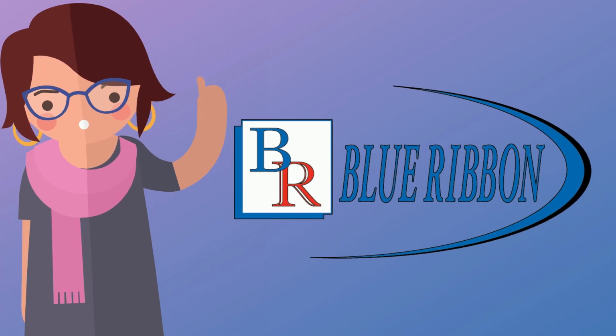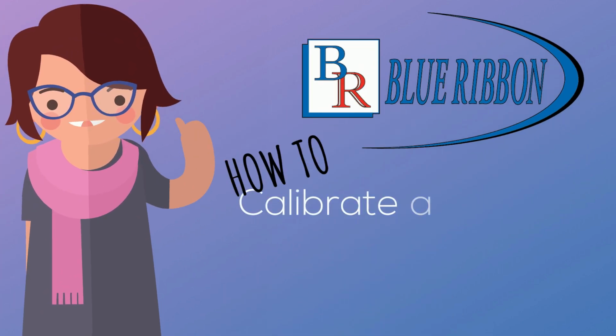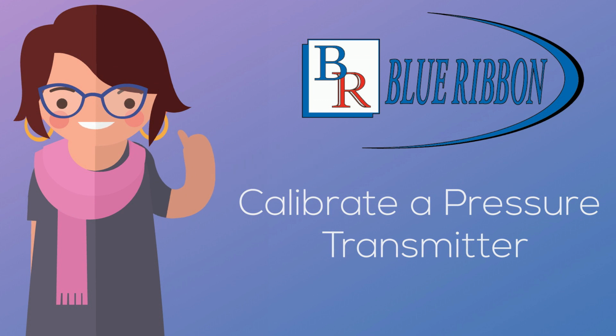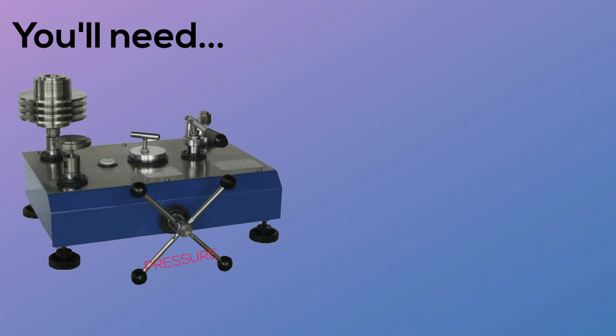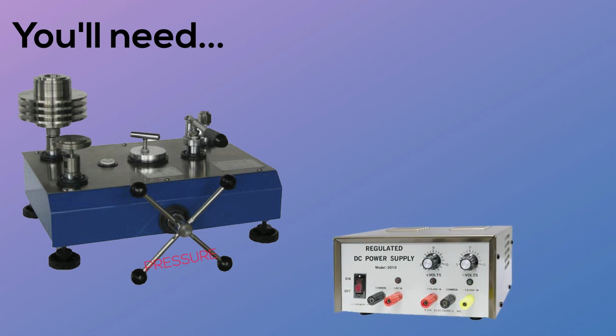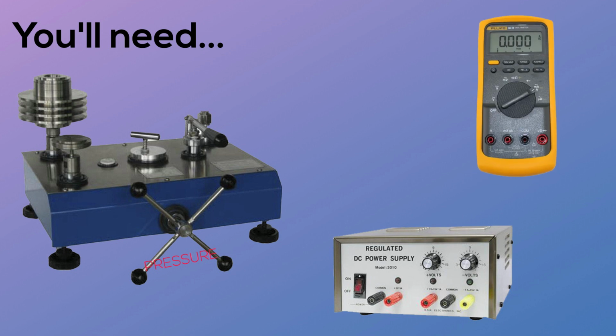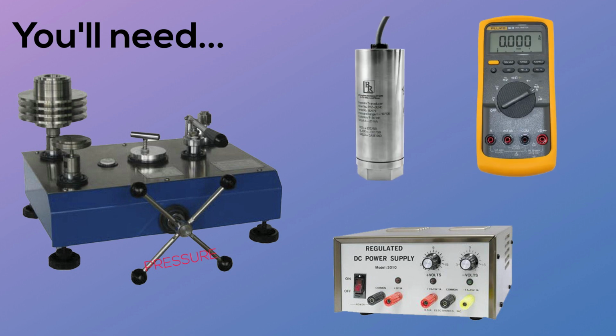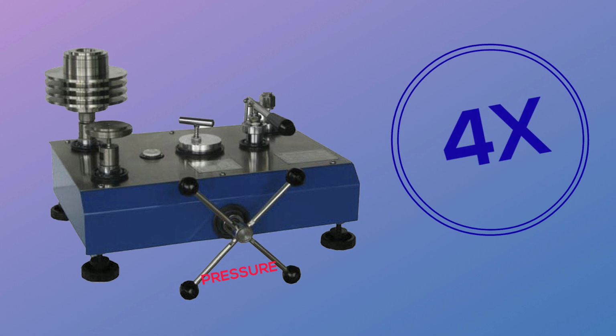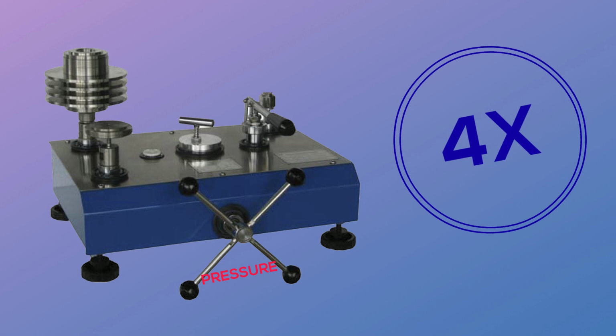In this video, we will discuss the basics of how to calibrate or verify a pressure transmitter. You'll need an adjustable pressure source with a pressure standard. In this example, we use a deadweight tester, a power supply, and meter to read the transmitter's output. We are also using a 4 to 20 milliamp loop-powered device, but this procedure can be used for voltage or millivolt units. A general rule of thumb is to use a pressure standard that is 4 times more accurate than the unit under test.